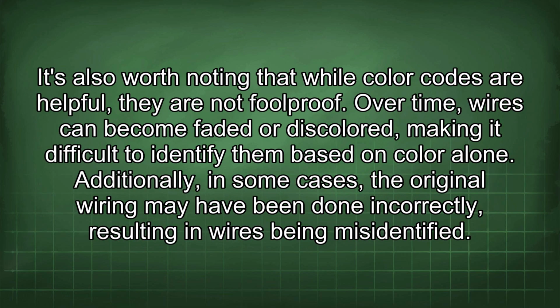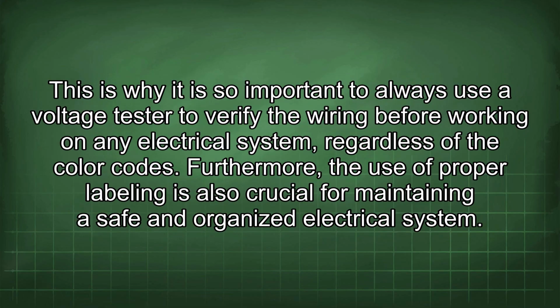It's also worth noting that while color codes are helpful, they are not foolproof. Over time, wires can become faded or discolored, making it difficult to identify them based on color alone. Additionally, in some cases, the original wiring may have been done incorrectly, resulting in wires being misidentified. This is why it is so important to always use a voltage tester to verify the wiring before working on any electrical system, regardless of the color codes.